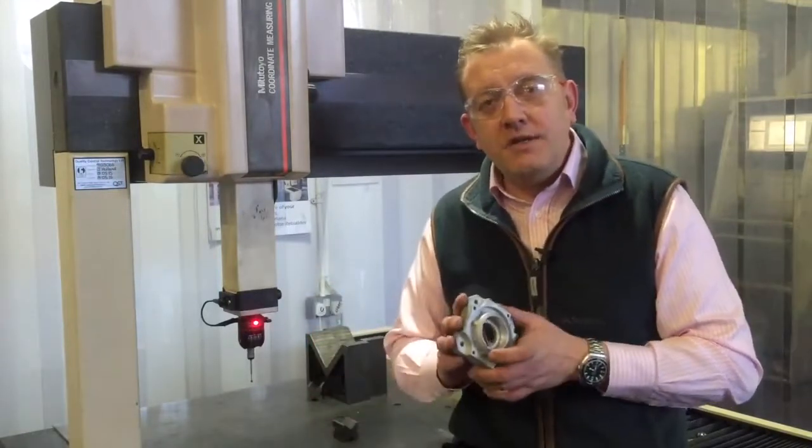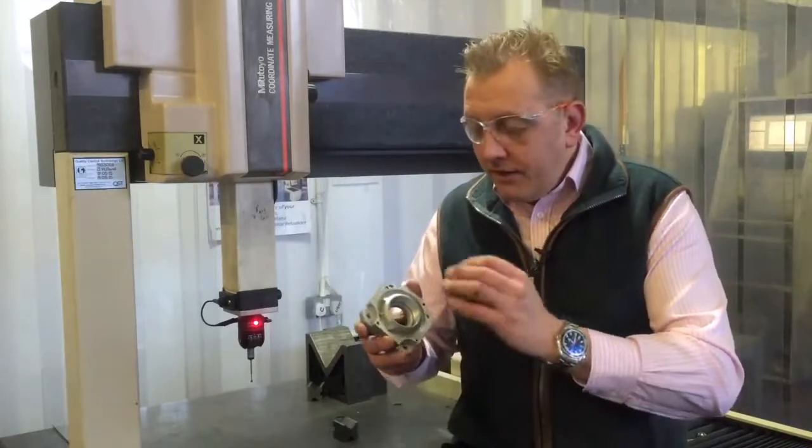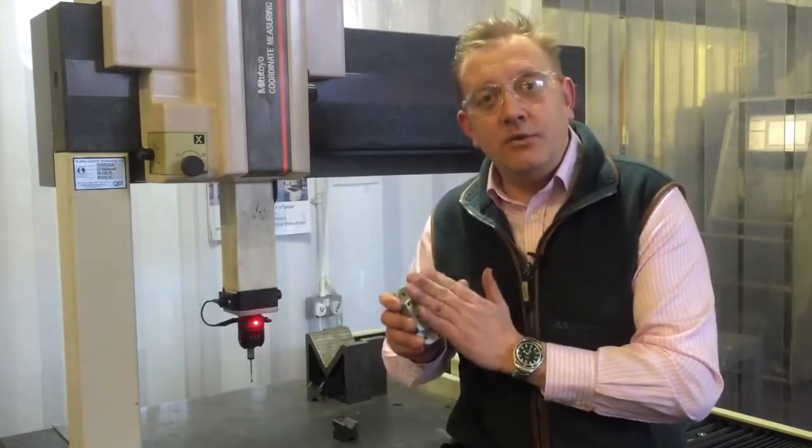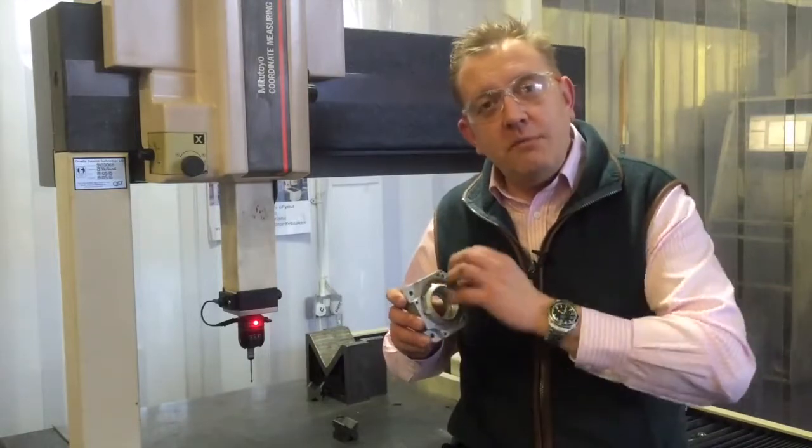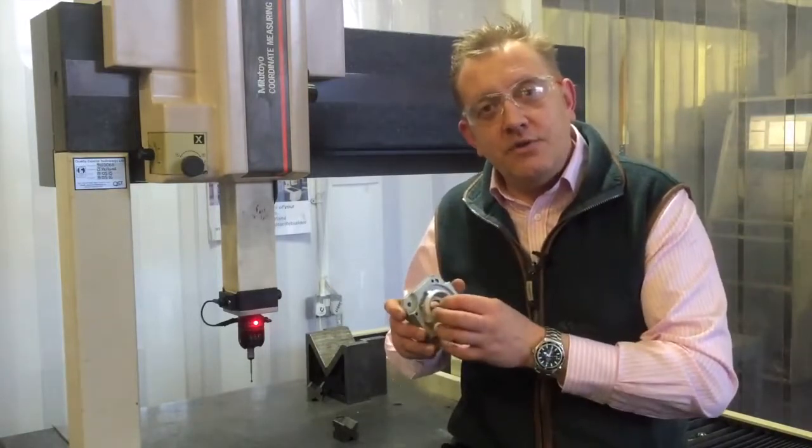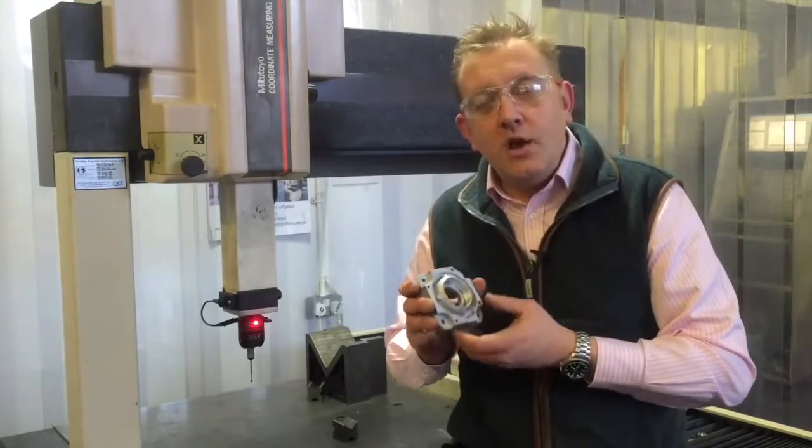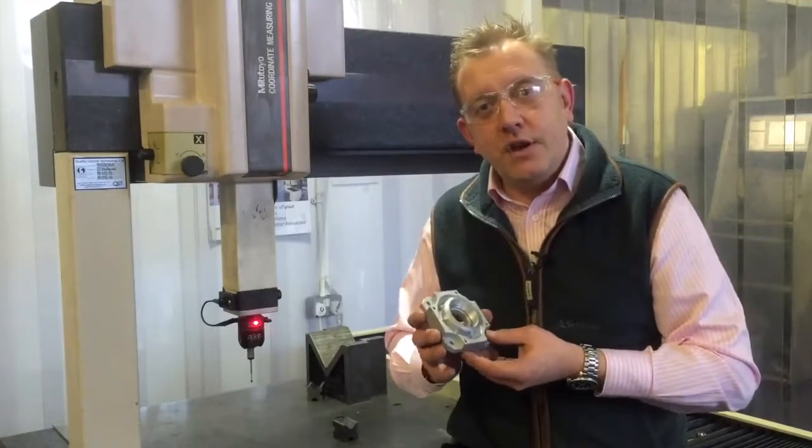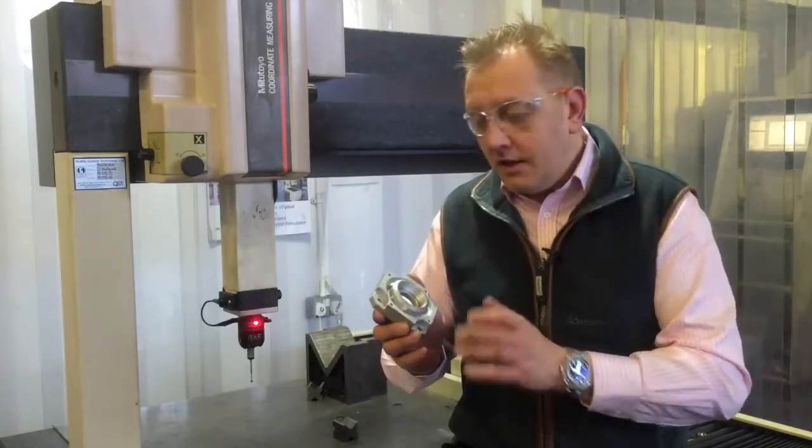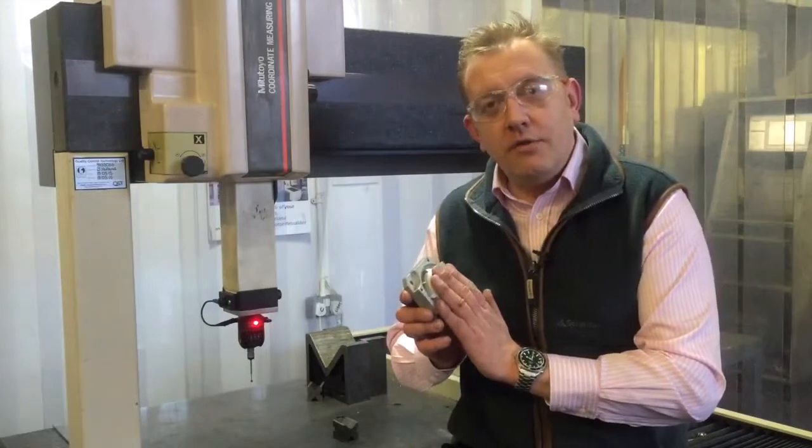It does not sound a great deal, however when the bearing sits in there it will be loose. The motor will work but over time the bearing is going to spin in the housing and create further problems. We like to get repairs right first time so the measurement is done correctly, sleeving will be carried out, and we know the fits are correct.